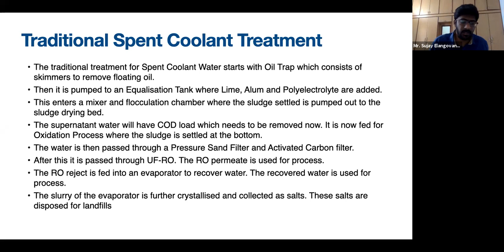It is now fed for an oxidation process where sludge is settled at the bottom. The water is then passed through a pressure sand filter and activated carbon filter. After this, it is passed through a UF and RO. The RO permeate is used back in the process. The RO reject is fed into an evaporator to recover water. The recovered water is used for the process. The slurry of the evaporator is further crystallized and collected as salts. These salts are disposed of in landfills or resold if they have value.